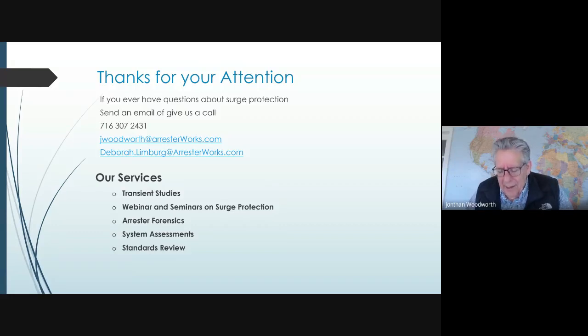Well, again, it's very situational. If the arrestor is in a substation and it doesn't function properly, they're supposed to stay together, not blow up. They're designed to not ever come apart. But if it malfunctions and comes apart, it can be dangerous to people if they're in the substation. It can be dangerous to the equipment and cause serious damage to the equipment. So it can be dangerous.